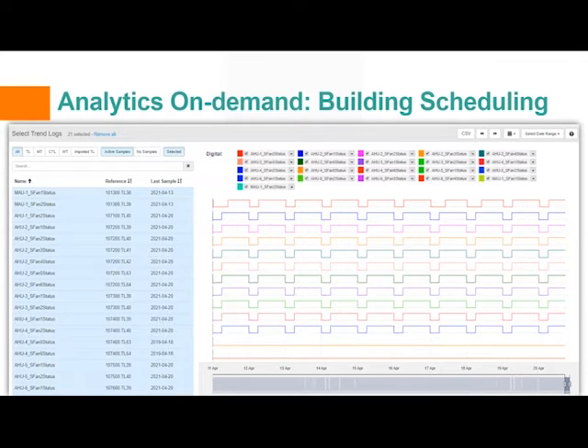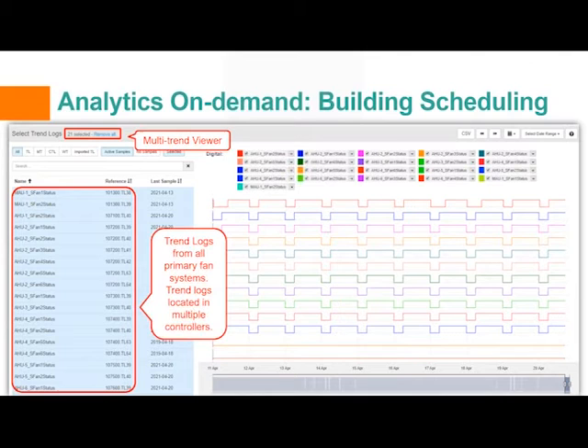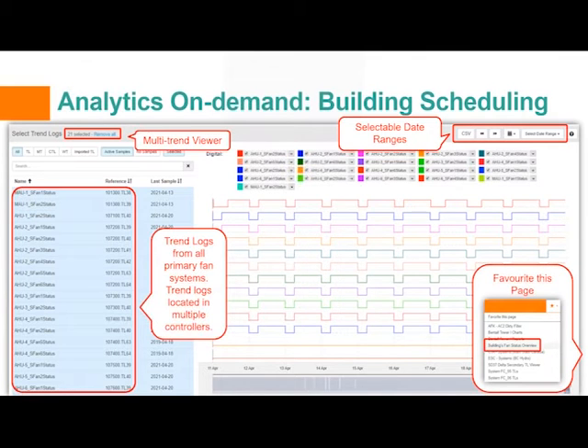One of the benefits of using an analytics platform is visibility of multiple systems, regardless of which BAS device is controlling them. Here's an example showing 21 trend logs from primary fan systems. We have selected the supply fan status points for each air handling unit and makeup air unit. In the upper right corner, we have the ability to select different date ranges to show a day, week, month, or year. In this example, we are looking at a 10-day period starting on April 11th. We also have the option to favorite or save this page so that it can be quickly accessible at any time during the commissioning process.